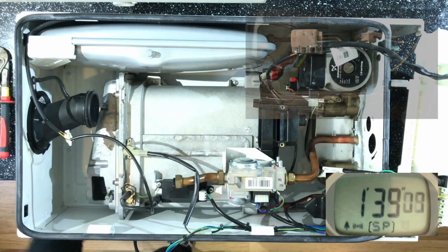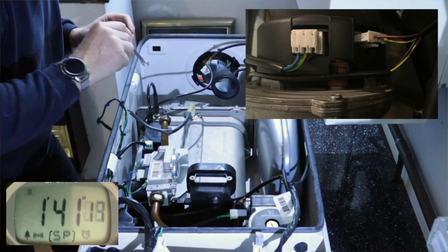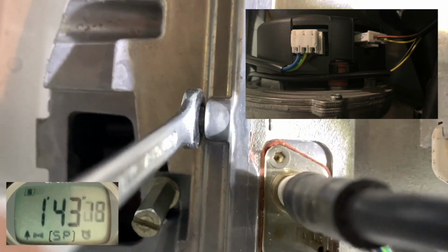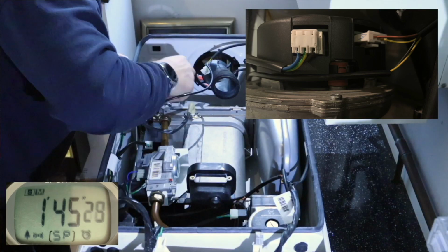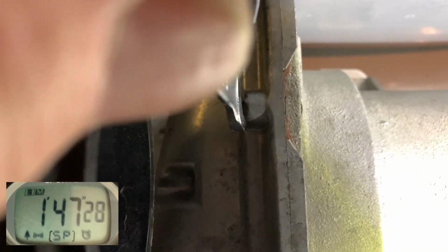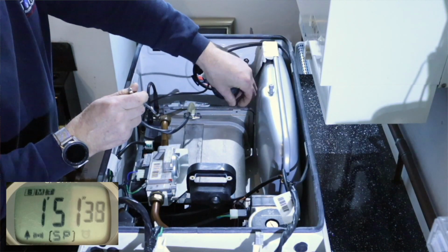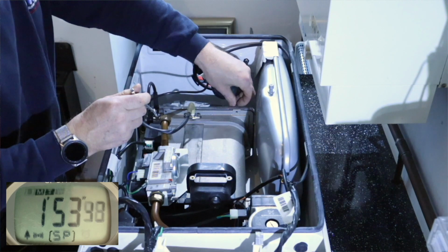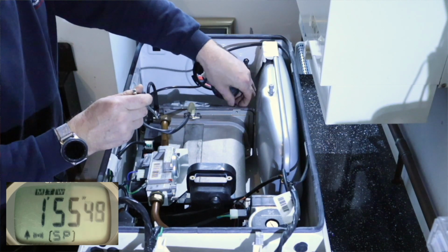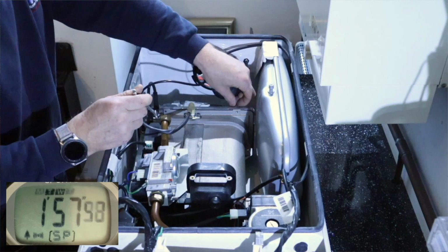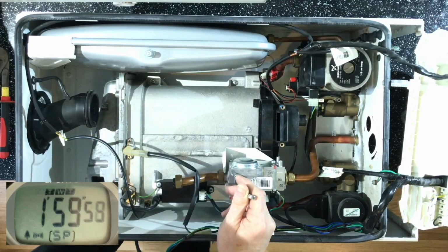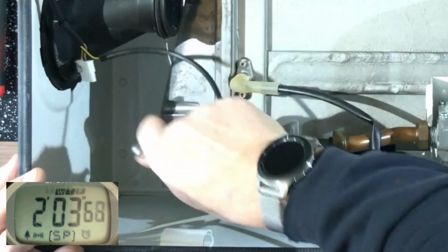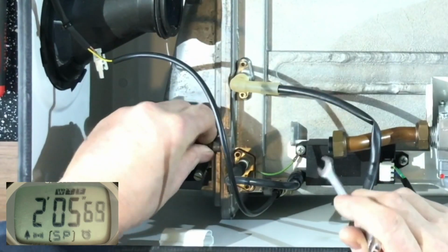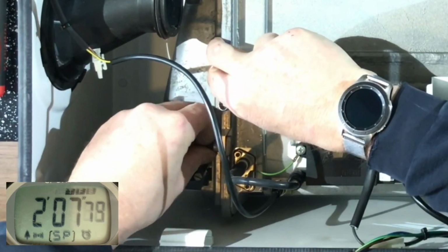So there are two electrical connections. One is 230 volts AC, which the fan motor electrics convert to 330 volts DC to drive the fan, so we need that energy to drive it. The other connection adjusts the speed of the fan between 1.5 and 2.7 volts DC. This connection is known as the pulse width modulation connection, or the PWM. The gas rate is increased and decreased depending on how fast the fan goes.